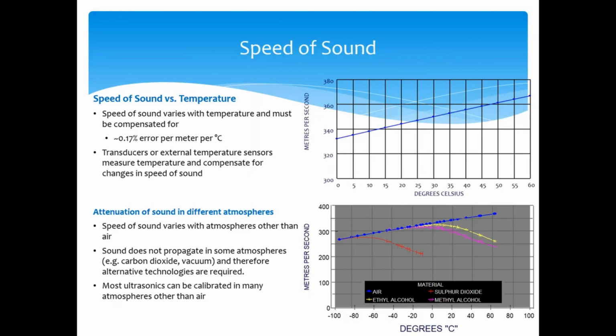The takeaway there is if the vapor space above your liquid level is air, then we're great with ultrasonic. If it is something other than air, be it off-gassing from sodium hypochlorite, sulfuric acid, whatever the case might be, that's going to affect the speed of sound through that particular media, which we show here, and that's going to have an impact on the accuracy of your level measurement. It's not that you won't make a measurement, it's that your accuracy will be affected.